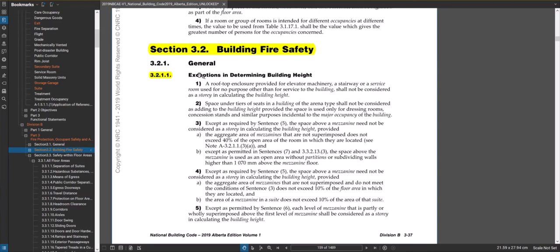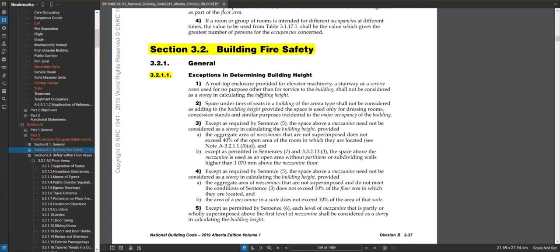So the very first article in 3.2 has exceptions to determining building height. You'll see the rooftop enclosure for elevator machinery, a stairway if it went up to the roof, or service room used for no purpose other than for the service of the building shall not be considered as a story in calculating building height. So you don't have to consider that mechanical room, a stair overrun, or an elevator overrun in building height and that's where that answer lies.